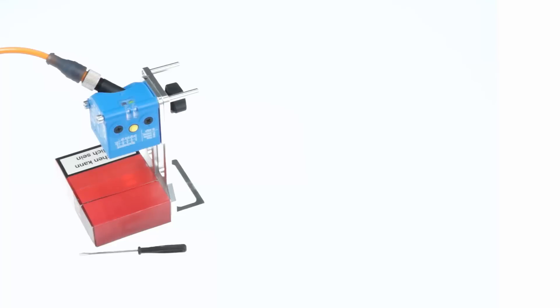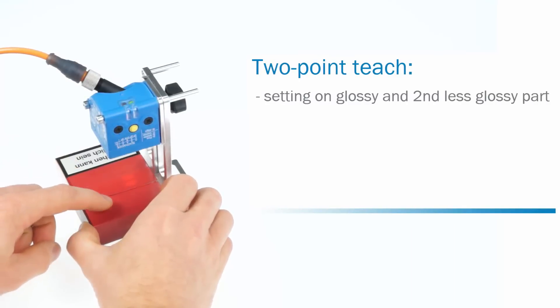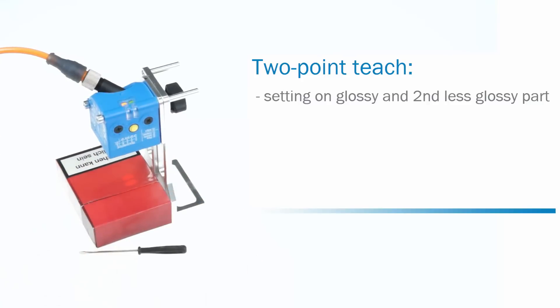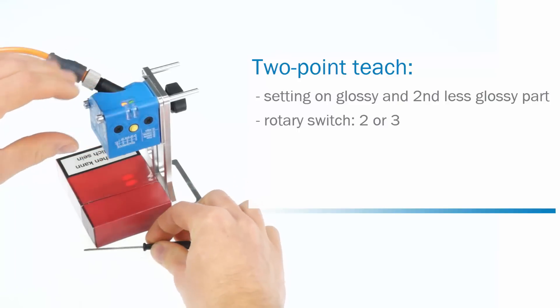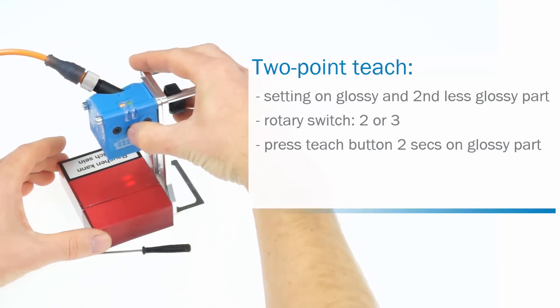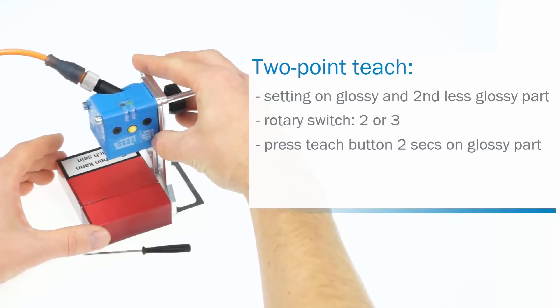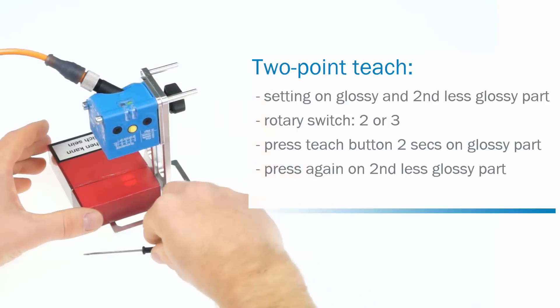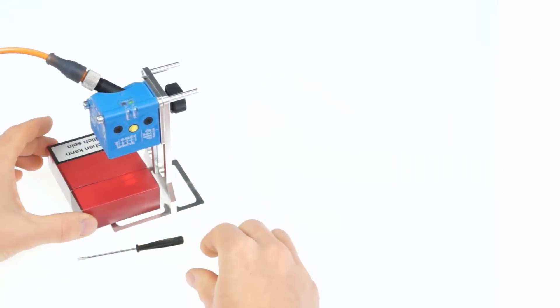The second method is the two point teach. This method requires adjustment on the glossy part that shall be detected and on the second less glossy part of the object. It is used for applications where the sensor should switch between two defined gloss levels. Set the rotary switch to two, or respectively three for the inverted Q output. Move the glossy part under the light spot and press the teach button for two seconds. The yellow LED starts flashing. Then move the second less glossy part under the light spot and press the teach button again. The sensitivity can be adjusted by setting the other rotary switch to A, B, or C.